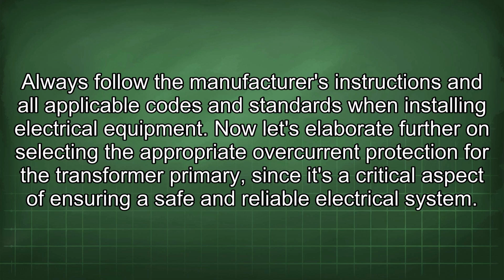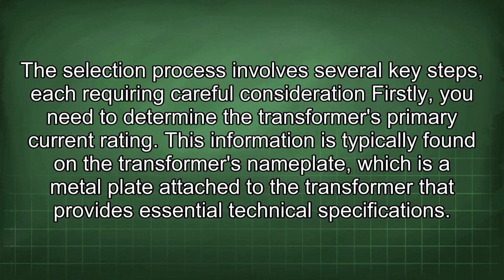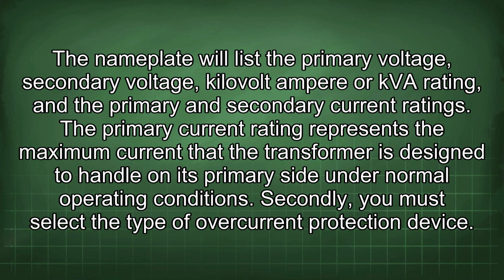Now let's elaborate further on selecting the appropriate overcurrent protection for the transformer primary, since it's a critical aspect of ensuring a safe and reliable electrical system. The selection process involves several key steps, each requiring careful consideration. Firstly, you need to determine the transformer's primary current rating. This information is typically found on the transformer's nameplate, which is a metal plate attached to the transformer that provides essential technical specifications. The nameplate will list the primary voltage, secondary voltage, kilovolt ampere or kVA rating, and the primary and secondary current ratings. The primary current rating represents the maximum current that the transformer is designed to handle on its primary side under normal operating conditions.